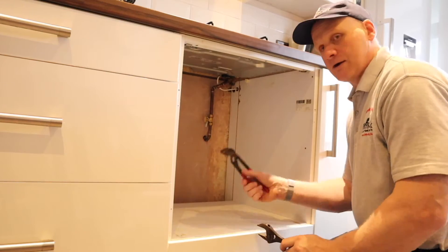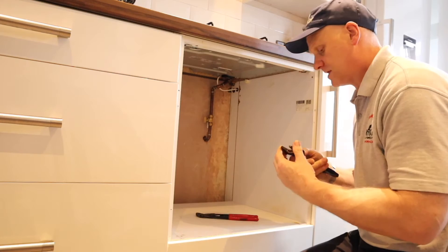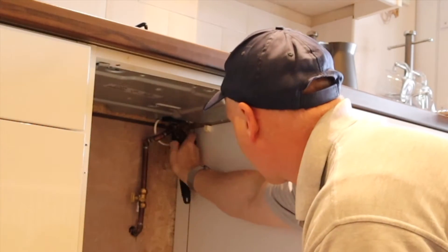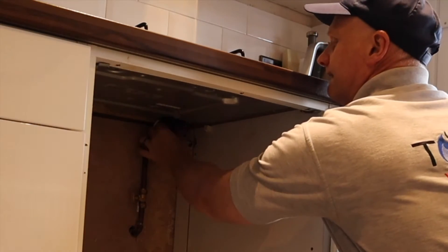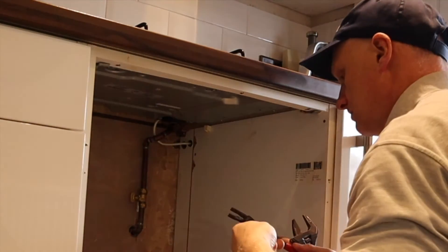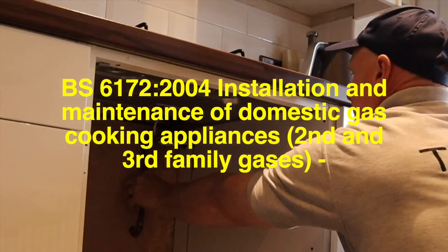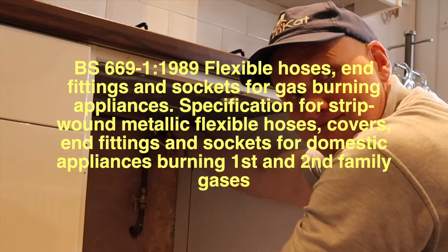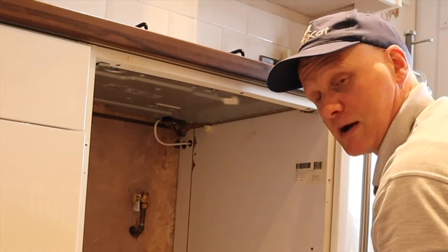We're going to take off the nut here and the nut here so we can remove this hob and get the gas out. It's always a hot topic of discussion in the gas industry whether a hob can be installed with a cooker hose or not. Technically it can, if the manufacturer's instructions say you can, the hob is installed to BS 6172, and the hose itself is manufactured to BS 669 Part 1. But I would always pipe it with rigid pipe myself.